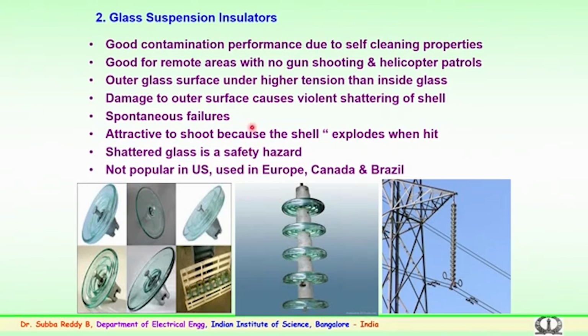So, again the outer glass, the glass which is being used, is under high tension compared to the inner side. Sometimes the failures or shattering happen on the outer surface with a violent shattering of the shell. Sometimes spontaneous failures also have happened in the field. As mentioned, it is attractive to shoot because the shell explodes. So, some people take it as fun and try to bring down or shoot the insulator. Later, the shattered glass is a safety hazard, and disposing of these shattered glasses is an environmental issue.